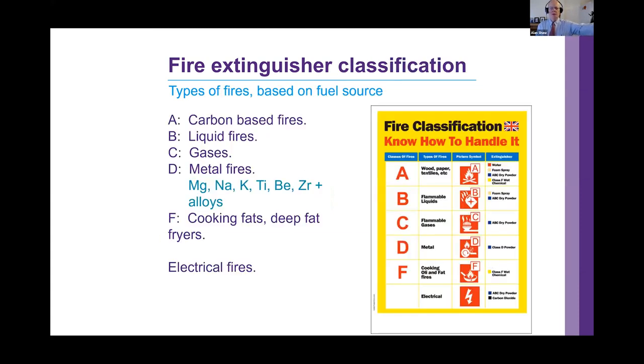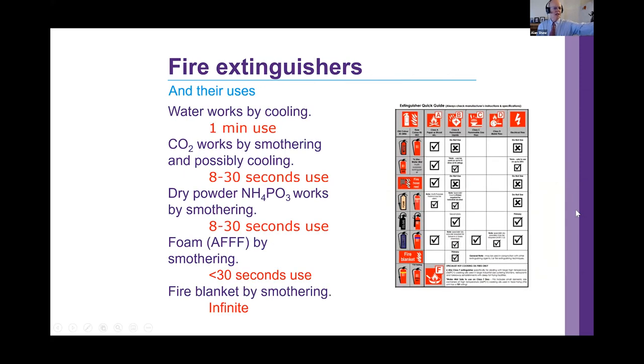This gives you a breakdown of fire classes: A, B, C, D for metal fires, and F for hot fat fires. One minute's use for water, up to 30 seconds for CO2 — maybe a bit longer if it's five kilos, but not much. Dry powder again about half a minute, foam about half a minute.